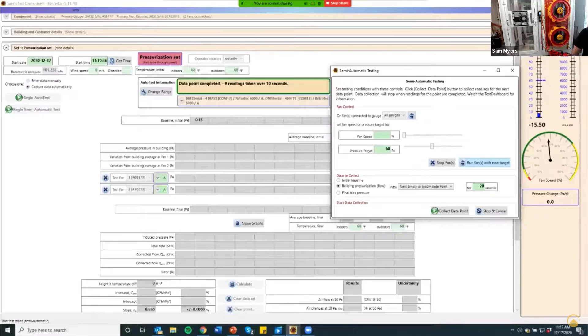It usually takes a 20-second reading. If you notice, the outline of this box is yellow, and whenever the reading is good and it has good data, it turns green and says the target has been attained. Now that the fans have balanced out, I can go ahead and tell it to collect that data point. Hit OK, and now it's collecting the data at that pressure for 20 seconds.